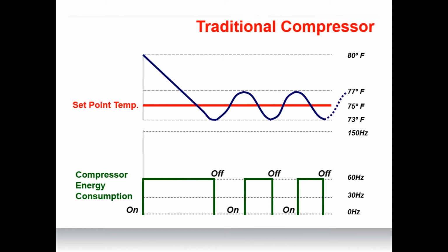So when we talk about the big difference between VRF and traditional heating and cooling systems, it ties back to the compressor. A traditional compressor system maintains temperatures by turning on and off depending on the set point. This means they're constantly ramping up and down in order to keep the temperature. They're drawing maximum energy input each time the system starts, so you get these big energy spikes. When the system turns off, the set point temperature naturally drifts and it's no longer maintained, it's no longer comfortable. Traditional compressor systems also employ a constant fan speed to deliver comfort to the entire zone, the entire home. When the system reaches the set point, the fan then just shuts off. So that's where you have these set point drifts as well as these energy spikes.